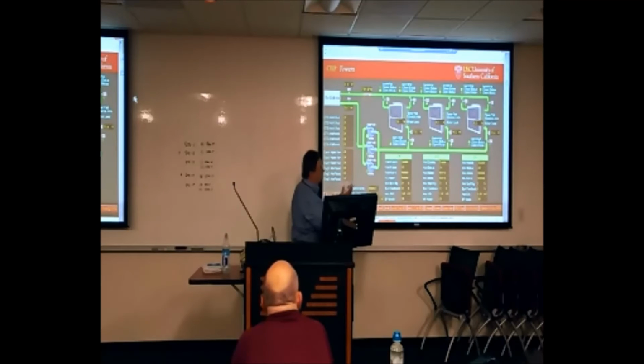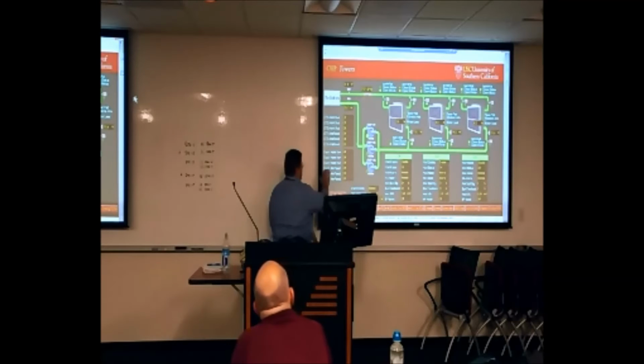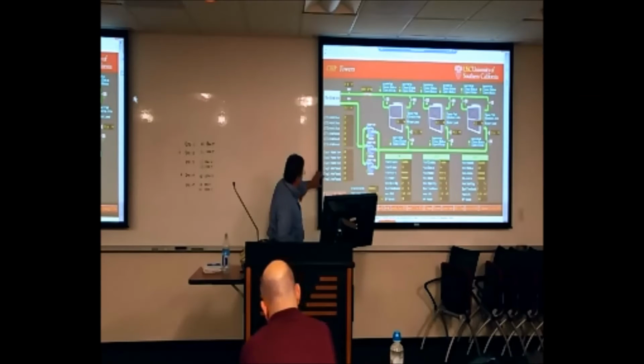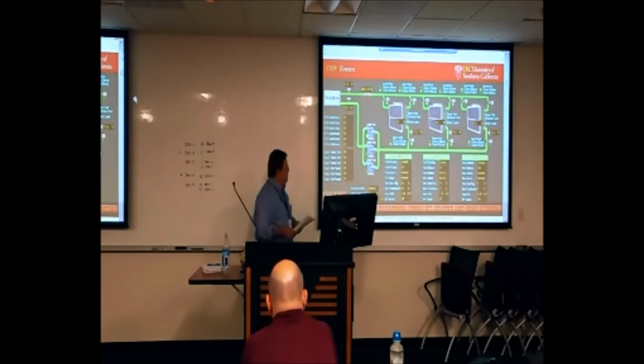So an alarm reset has to be activated in order to unlock the pump. So upon a pump failure, someone would go and fix the drive or look at whatever the issue was, and then someone would have to go through this graphic and hit the alarm reset switch right here in order to put that pump back into service. So here's the condenser water pump data right here, pump 1, 2, and 3, alarm resets. And that, when you turn the point on, is when the alarm gets reset. You can leave it on, it's kind of a switch and forget point. Upon another failure, just turn it off, turn it back on again. On the switch to on is where that alarm clear is going to occur.